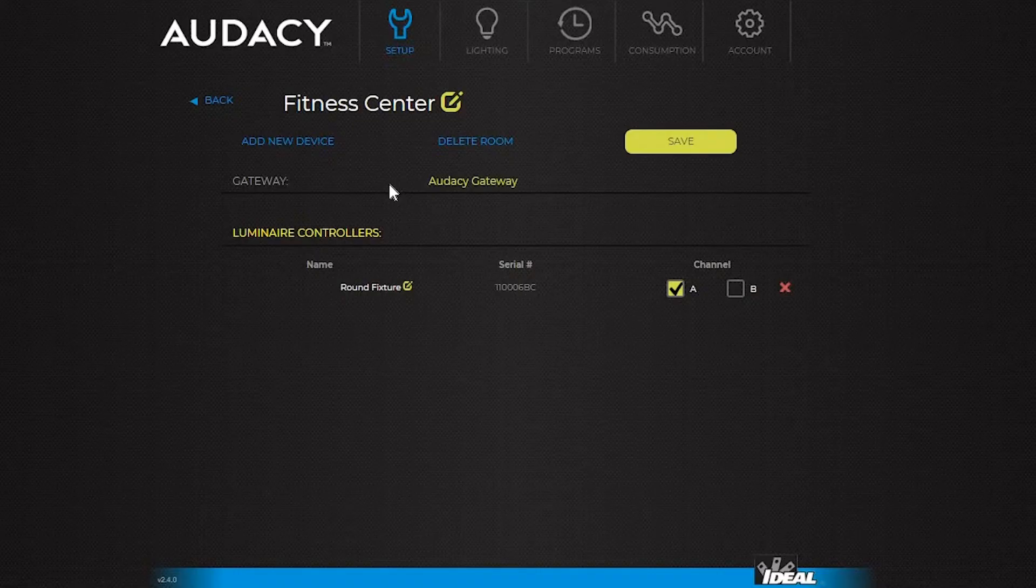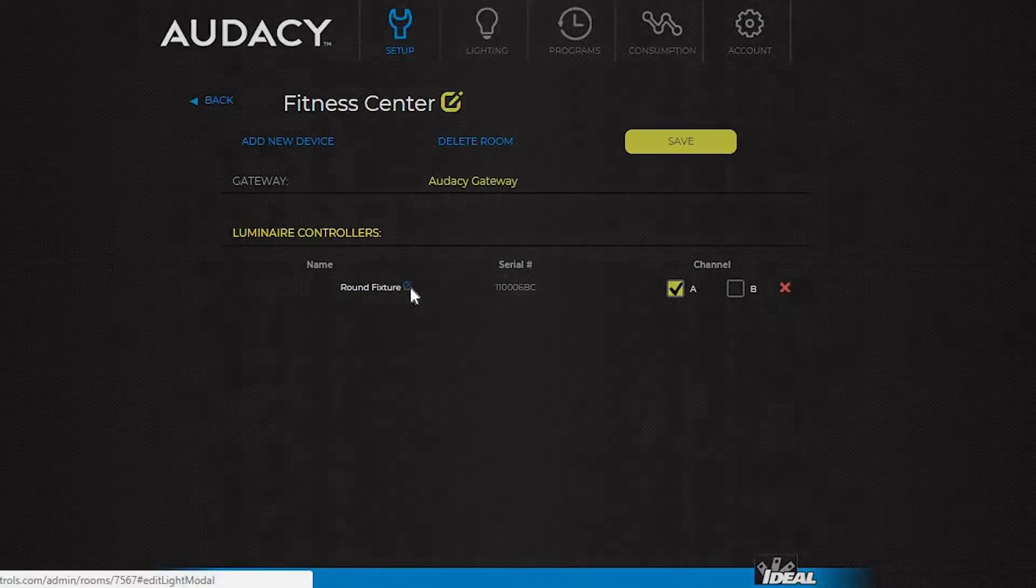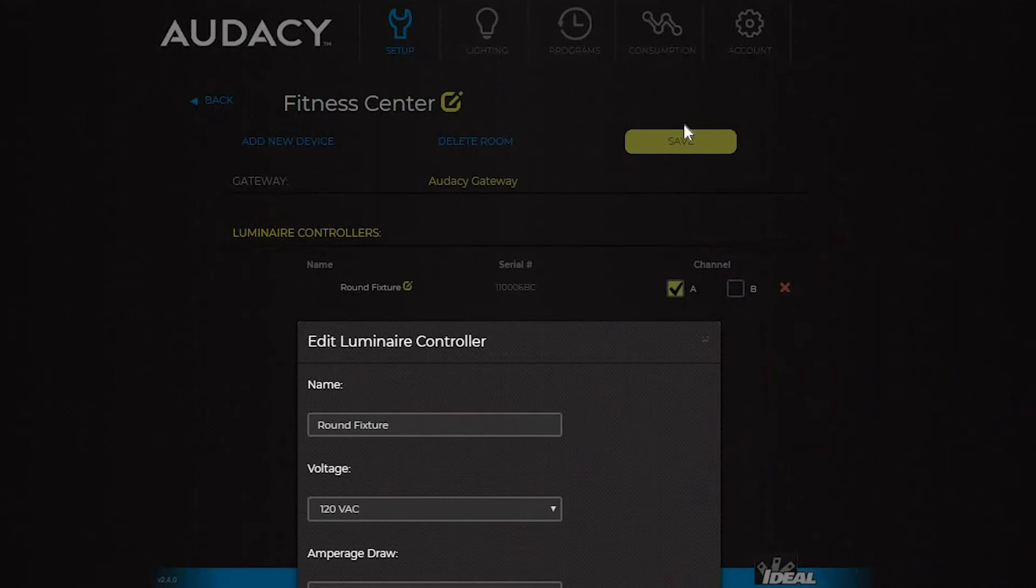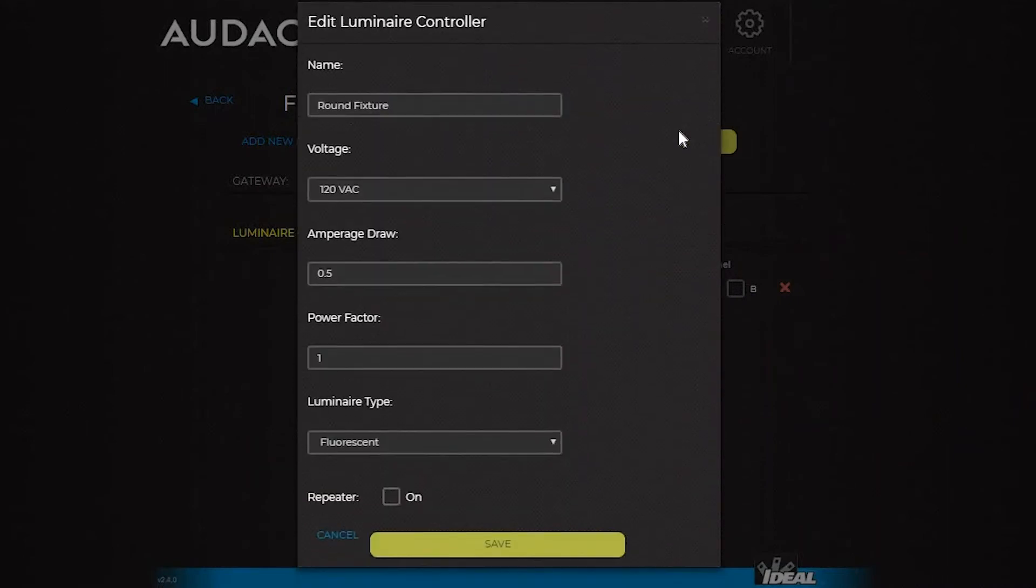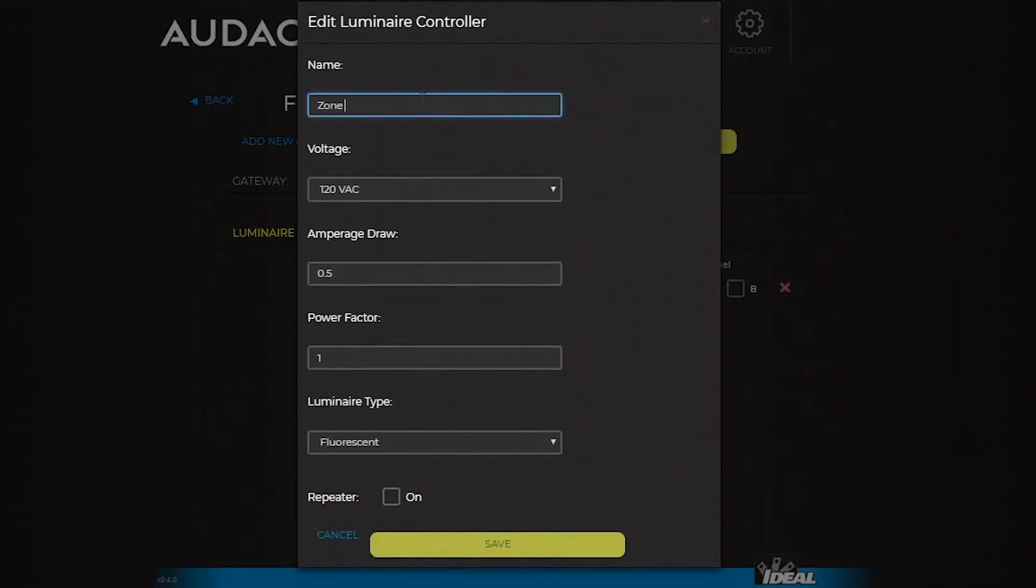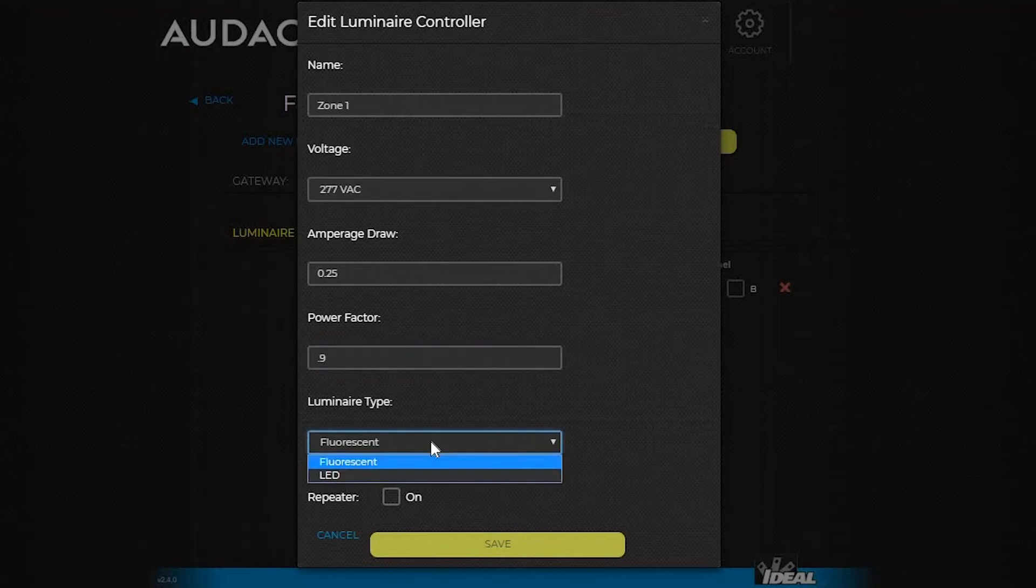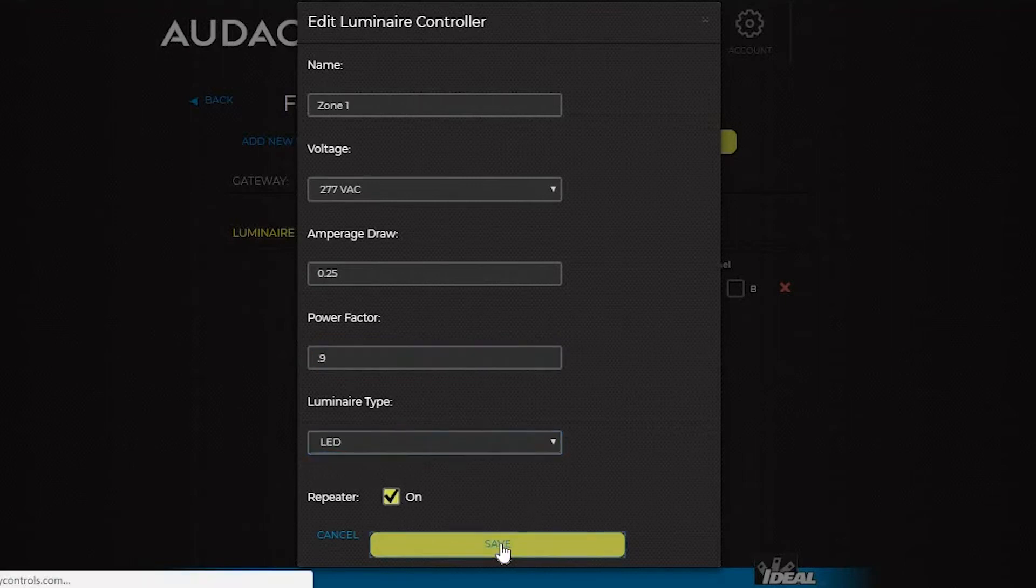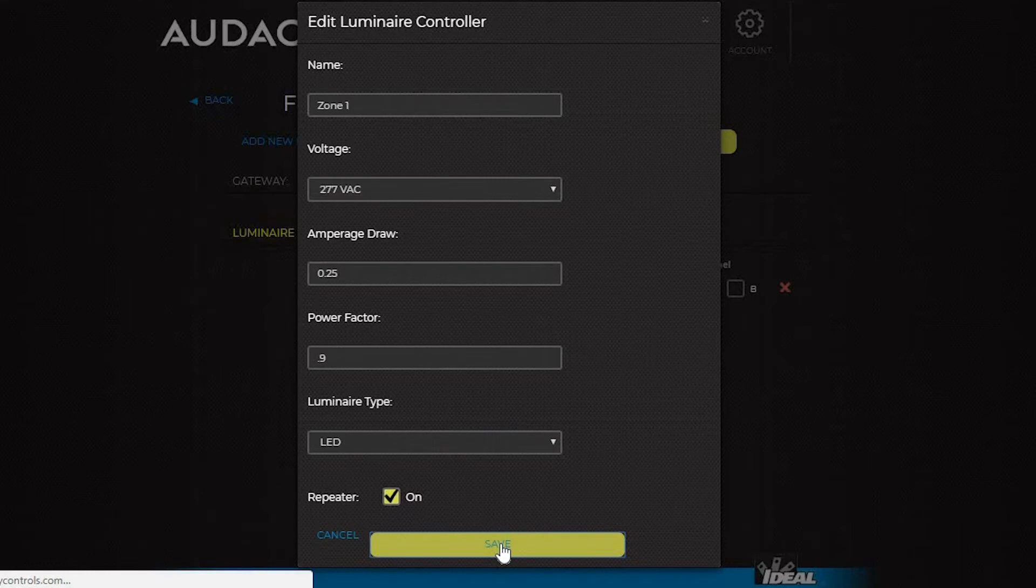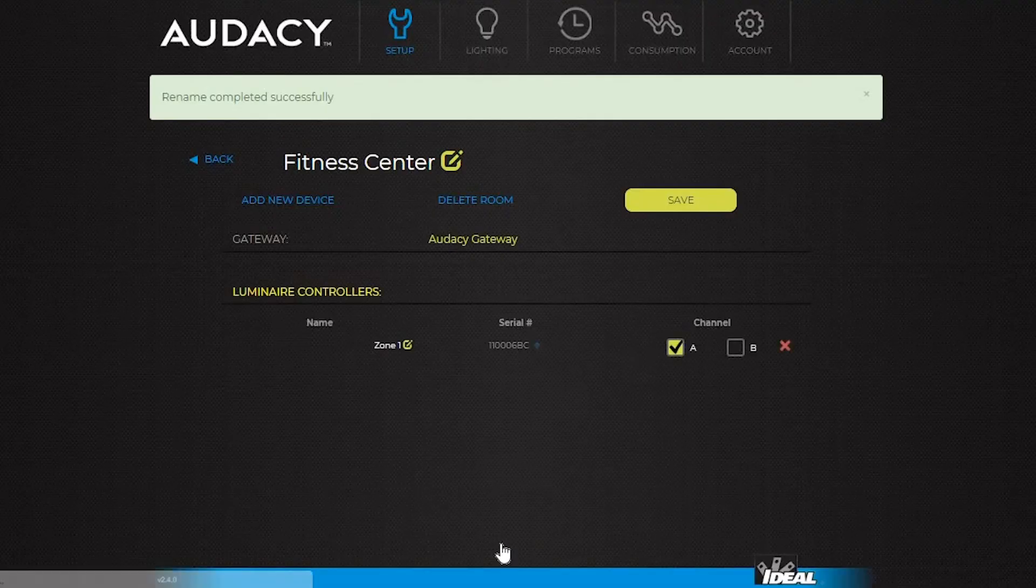To change the settings on luminaire controllers, click the edit icon. In the edit screen, you can change the device name, voltage, amperage draw, power factor, and luminaire type settings. This is also where you can set this particular controller as a repeater. Please note, enabling more repeaters in a system than are required for proper communication may have a negative impact on the system. Click save to save your changes.